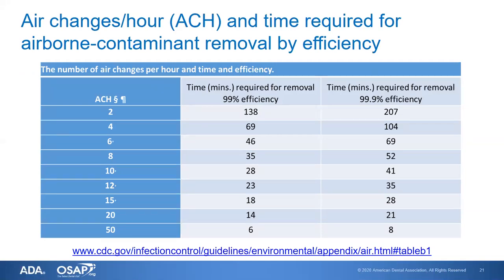Some people wonder how many air exchanges per hour are needed to clear a room of small particulates. There is a table provided in the CDC Infection Control Guidelines for Environmental Control. If you look at this chart, you'll see it's not a direct correlation between the number of air exchanges and the time required to remove particulates. For instance, if you had an ACH — air changes per hour — of two, you might think that means the air changes every 30 minutes, but that's not exactly the way it works, as the chart shows.